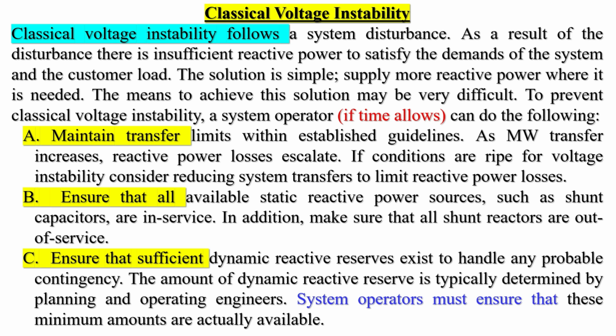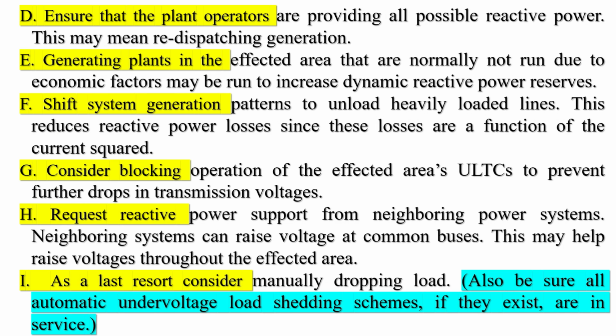C. Ensure that sufficient dynamic reactive reserves exist to handle any probable contingency. The amount of dynamic reactive reserve is typically determined by planning and operating engineers. System operators must ensure that these minimum amounts are actually available. D. Ensure that the plant operators are providing all possible reactive power. This may mean redispatching generation. Generating plants in the affected area that are normally not run due to economic factors may be run to increase dynamic reactive power reserves. E. Shift system generation patterns to unload heavily loaded lines.